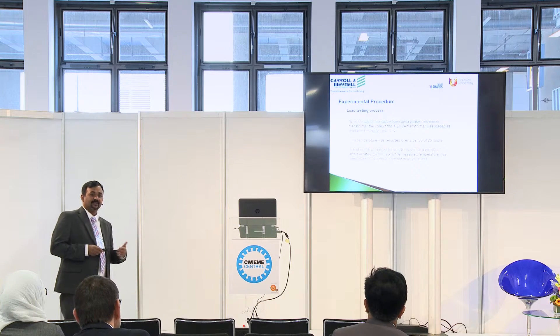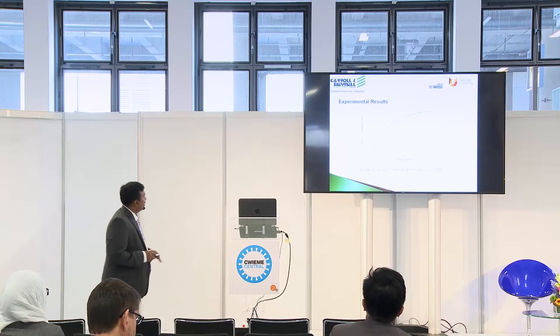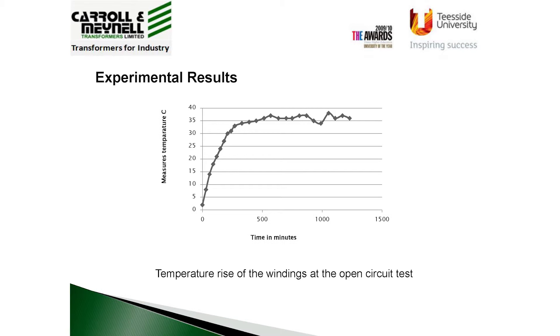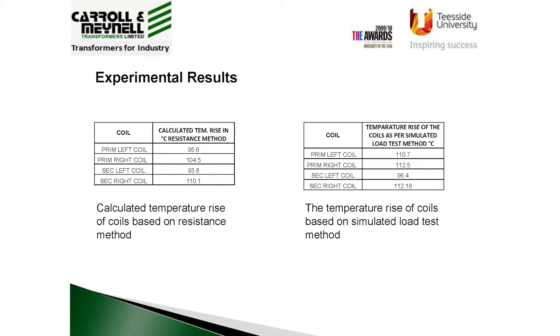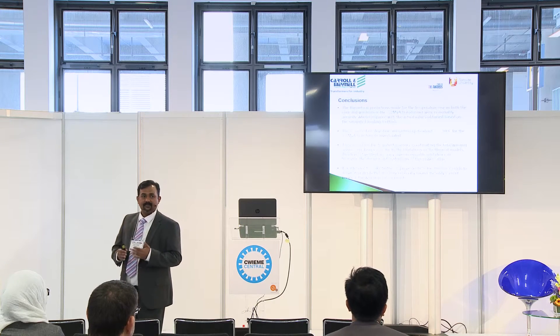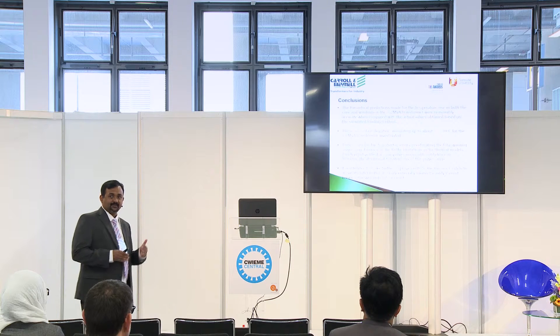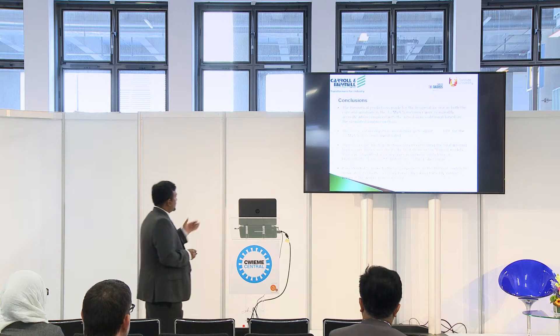The transformer was tested over a weekend: the core was tested for about 25 hours and another 25 hours for the windings. The temperature rises measured for the core and windings were then projected using the simulated loading method. We concluded that the transformer does not reach excessive temperatures during full load operation, which guarantees a long service life. It was constructed with a Class H insulation system, but we targeted temperature rise levels within the Class F range.